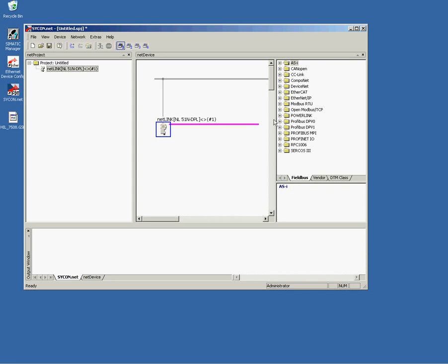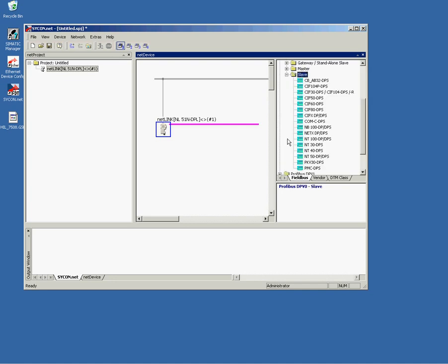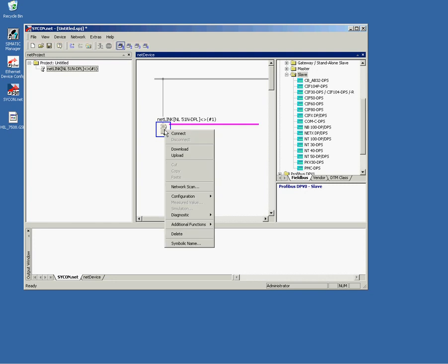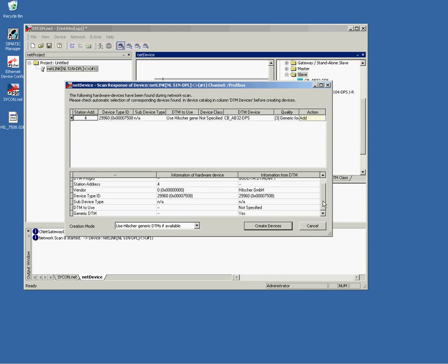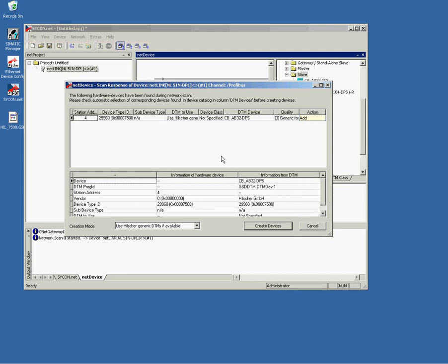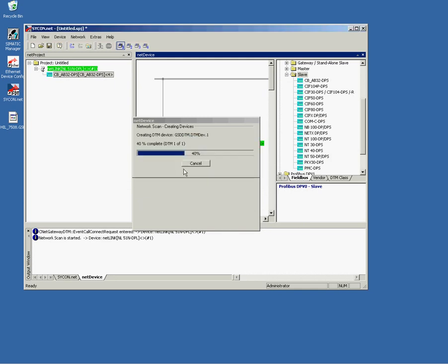The easiest commissioning you can imagine is the automatic network scan. Look, here is the GSD file in the device that I have imported. You can configure this device manually by drag and dropping it to the bottom line. But I am using the automatic network scan instead. A right click to the icon offers you this option. So, the scan will bring up all devices that are connected to the Netlink. Here you'll find my device. Since I have imported the GSD file before the scan, Sycon knows exactly the type and configuration of the slave that I have connected to the Netlink. At the end of the scan, we have to accept the new configuration and Sycon now will automatically configure Netlink's configuration.